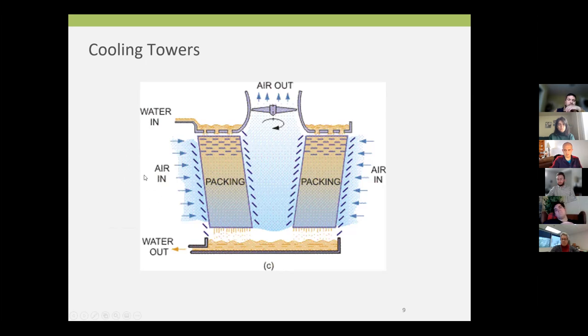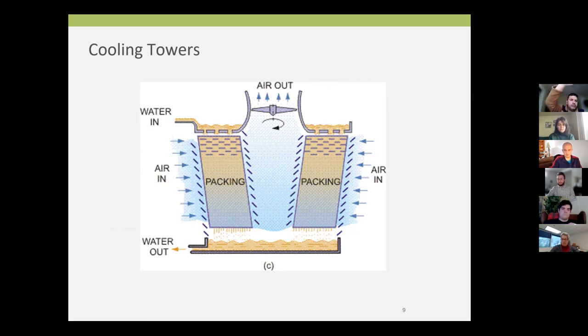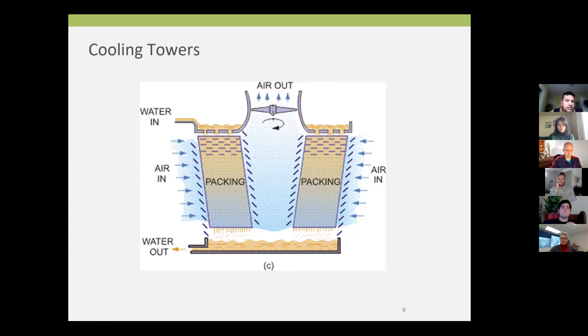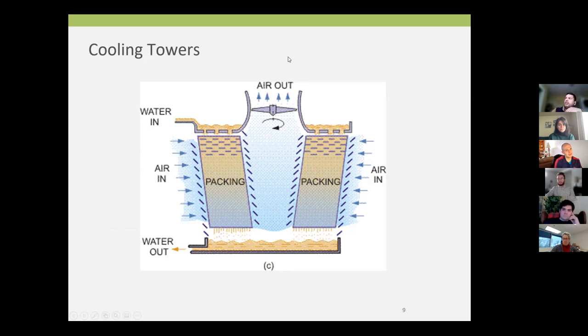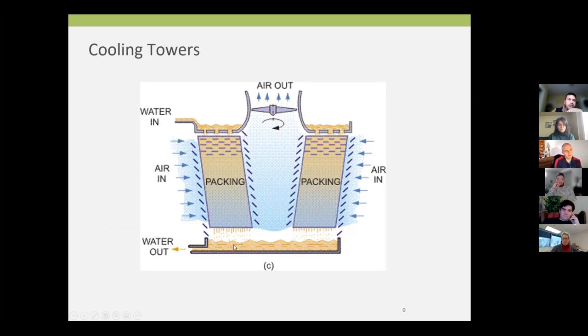Now, as this water is falling, the air gets accelerated. That dry air, 72 degrees with 25% humidity, or 100 degree air with 25%, gets accelerated through that media. The fan, the faster you spin it, velocity, faster you spin it, higher the velocity, the more air is going through here, the faster it picks up that heat. In doing so, yes, some water is lost. It gets evaporated. But what happens is it picks up that heat, and that water gets cooled down to the wet bulb temperature. And that water goes out, so the air coming out here is definitely more humid than it was going in. Going in, it was coming in at 25%. Here, it's probably coming out at 80%, 85%.